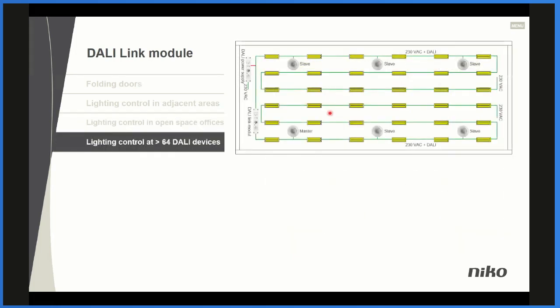As I said earlier, if you have more than 64 DALI devices on a DALI bus, there is a limitation due to the number of combinations that we have. It could be a stock room or a sports hall, where we have a lot of luminaires. That means we have a master and several slaves in order to cover the area. You can actually put in a DALI module here and a power supply to supply the other part of the DALI bus. That means you can have more than 64 DALI luminaires on one DALI bus if you do it like that. It could also be done in another way.